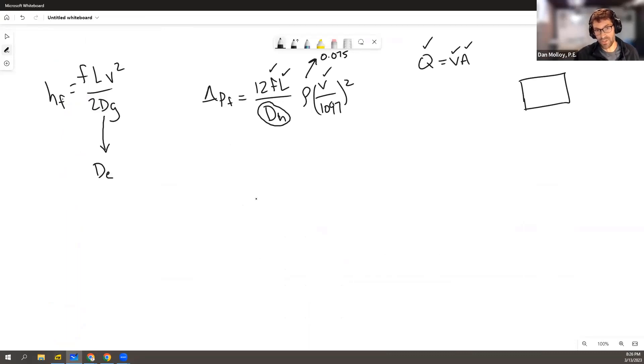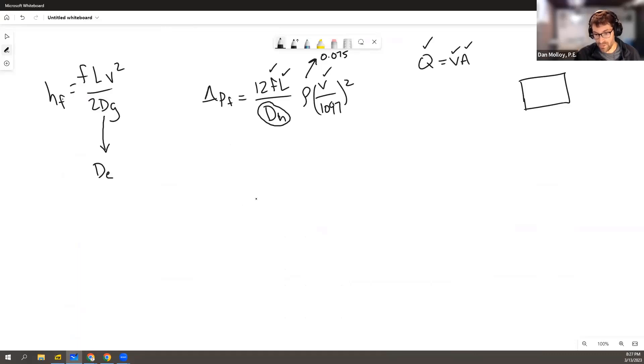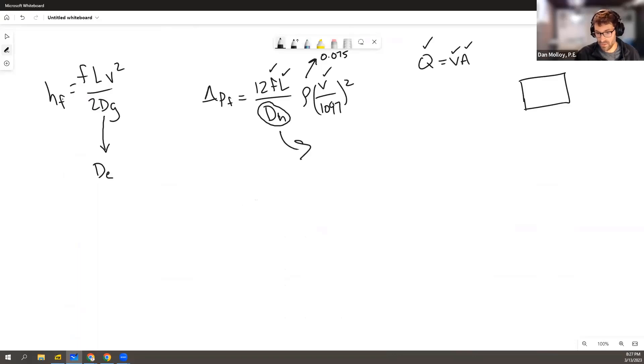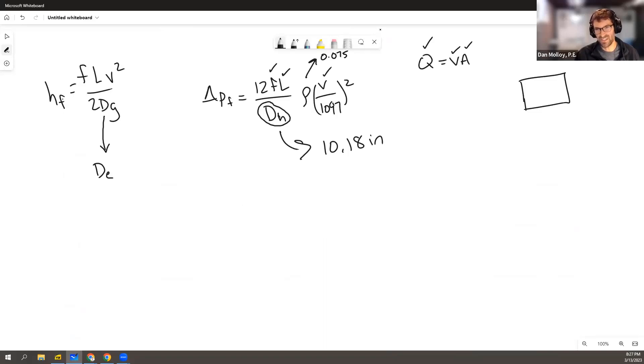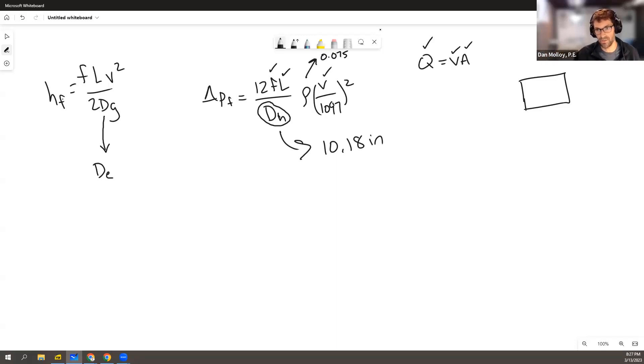So I worked this problem both ways, and I'll spare you the gory details. But if you do that, you get a difference between the hydraulic diameter, DH, turns out to be 10.18 inches. And by the way, for this equation, this has to be in inches. Everything else kind of works out. This has to be in feet per minute to go with the 1097. So this is kind of a rule of thumb equation where everything has to be in the right units going in.